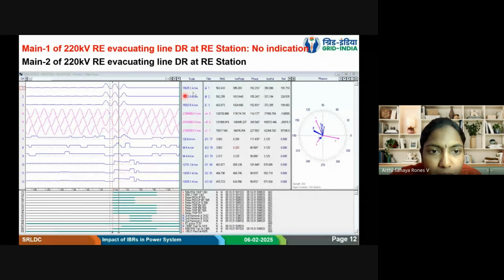If you see the currents, they're all in phase because it's a zero sequence component. It is the I naught, like IA, IB, IC is the same as the IN. So it is like a circulating zero sequence current. Conventionally, when a fault is there, only the fault B phase current will increase. Because of RE, we are seeing this kind of signature. This same amount of current would have reflected in the neutral. In this particular DR, we are not seeing the neutral IN, but it is the same current, that is the zero sequence current.